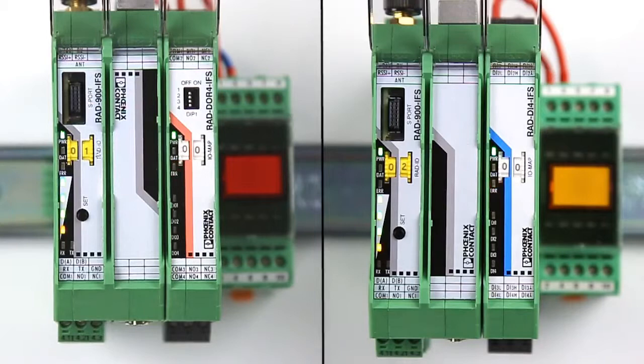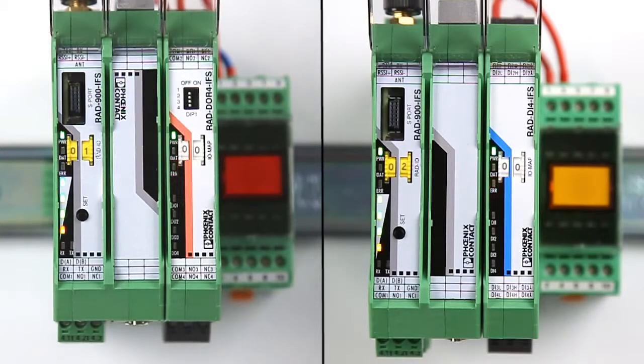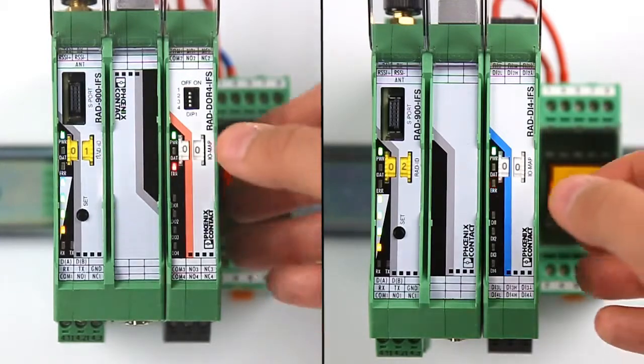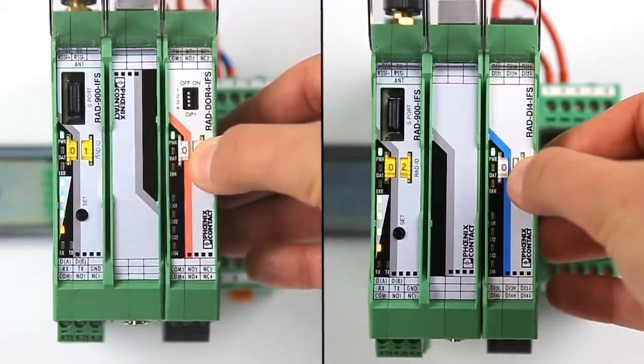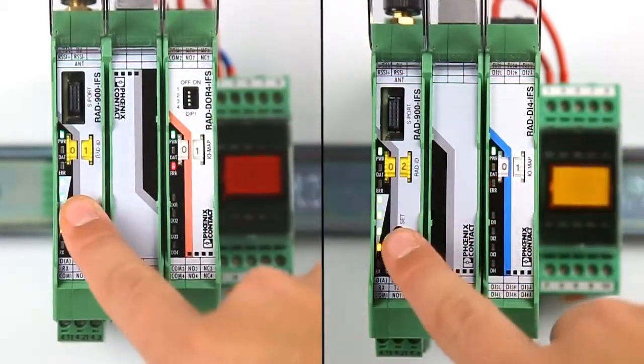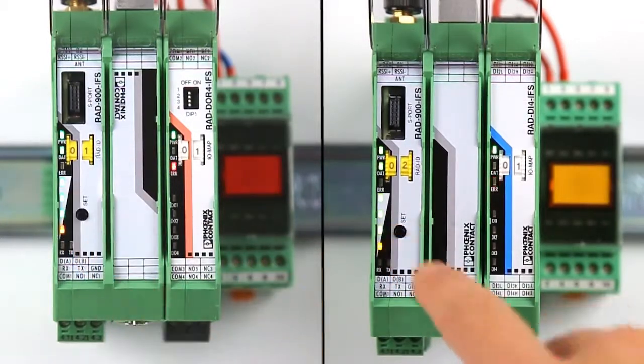To add these to the wireless network and map the I.O. modules, simply set an I.O. map address using the white thumb wheels on each I.O. module. Set them both to the same number and press the set button on each wireless module, enabling the detection of the I.O. modules.